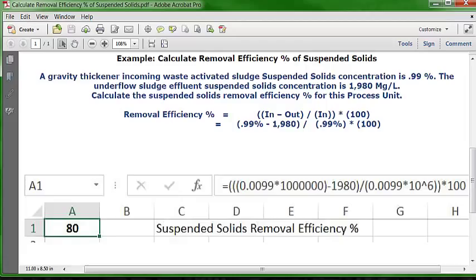Let's put this into the Excel spreadsheet. Type an equal sign, three open parentheses, then 0.0099 times one million, then one closed parenthesis. Subtract 1,980 and add another closed parenthesis. Divide by the incoming number again — 0.0099 times 10^6 — and add two closed parentheses. That gives the decimal equivalent of removal efficiency. Multiply the whole answer by 100, hit Enter, and the answer is 80%.